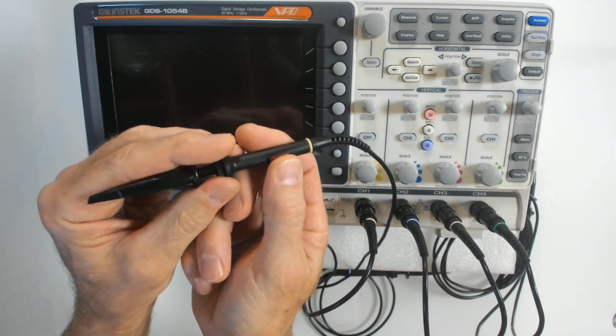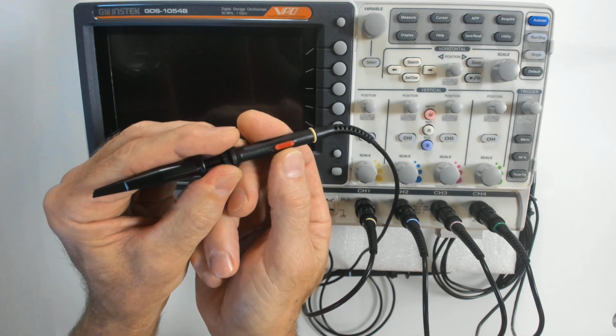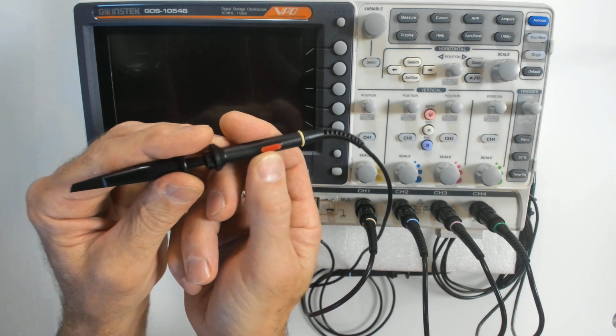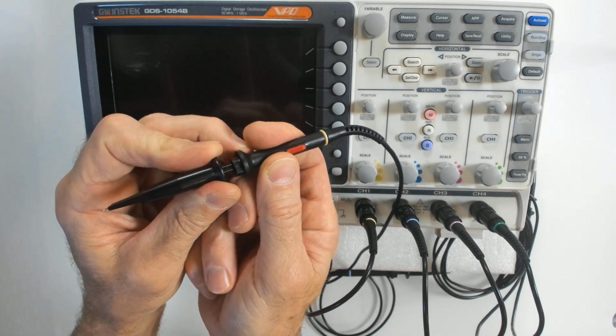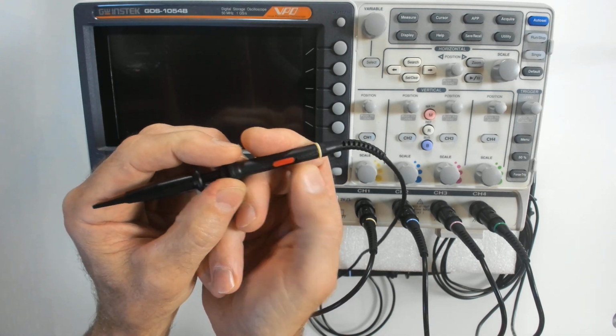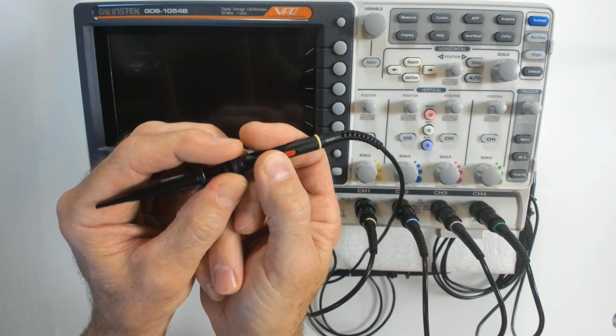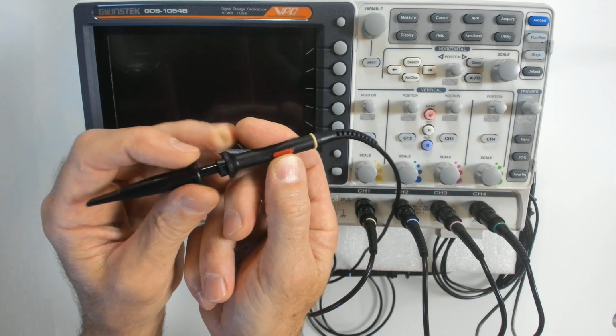Okay, so that's very important, to always keep an eye on where your selector switch is for your probe, because the scope has to be set to match that. Otherwise, your numbers are off by a factor of 10. Which is a good clue. If your numbers are off by a factor of 10, you might have bumped this switch without realizing it. That's a quick clue.